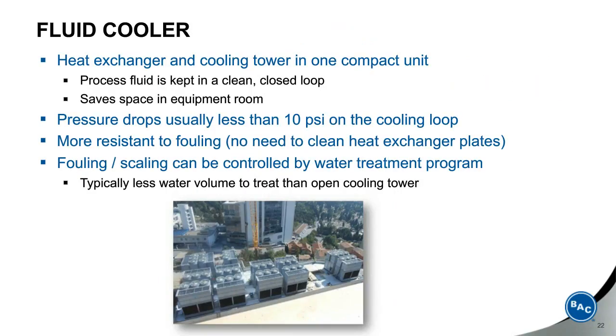Now, a fluid cooler combines the function of a heat exchanger and cooling tower in one compact unit. This keeps the process fluid in a clean, closed loop, and it also saves space in the equipment room by taking the heat exchanger and putting it outside with the cooling tower. Pressure drops are usually less than 10 psi on the cooling loop, which is the same as a plate and frame. It is more resistant to fouling.